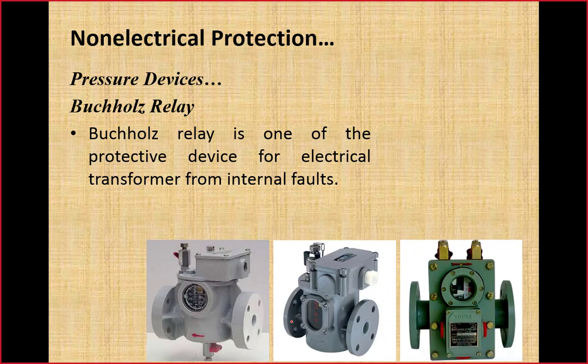So here are a few diagrams of Buchholz relays. The see-through glass is just for the visual inspection of the color of gases inside this Buchholz relay, and shortly we are going to discuss the working principle of Buchholz relay in detail. And the arrow that you can see here in front of this Buchholz relay is to help with the installation of these Buchholz relays on the top of the transformer tank.